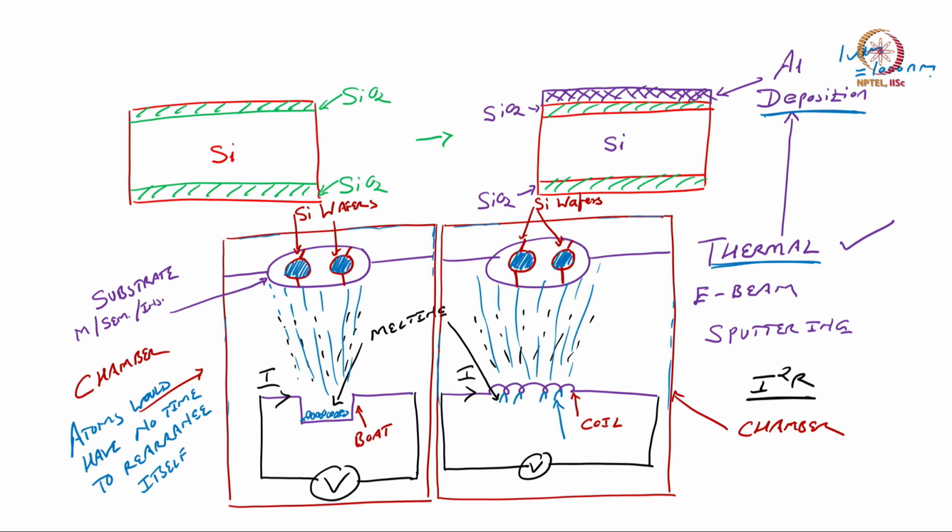How would I know it is 1 micrometer? So, we require another tool that is integrated inside this particular chamber, and that tool we call quartz crystal monitor, QCM.